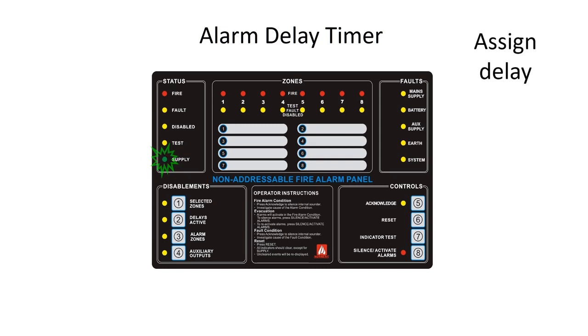Once the delay timer has been set and still in access level 3, press the Selected Zones button. The Selected Zones LED and the Acknowledge LED will flash. Press the Acknowledge button to confirm. The Acknowledge LED will continue to flash and the Selected Zones LED will be on.